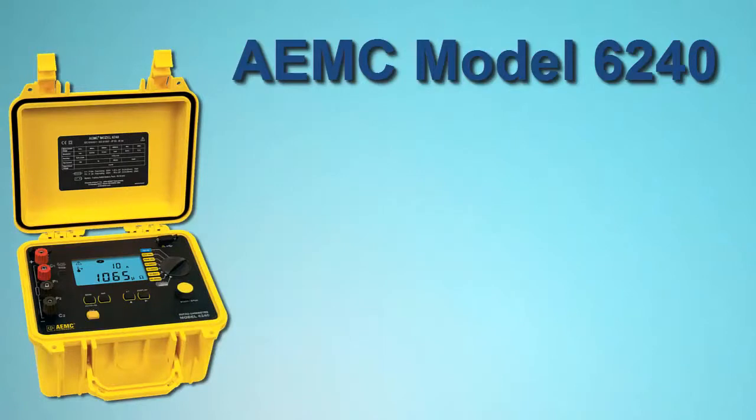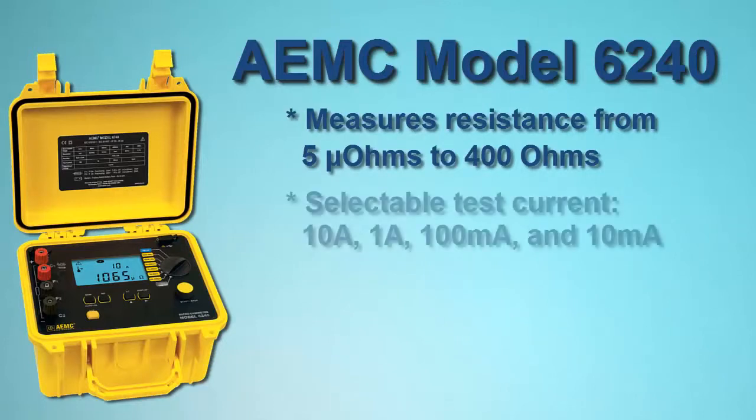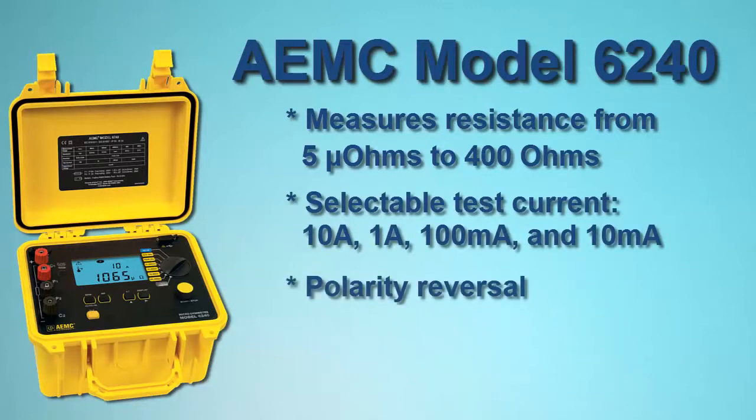The Model 6240 measures resistance from 5 micro-ohms to 400 ohms. The instrument provides selectable test currents of 10 amps, 1 amp, 100 milliamps and 10 milliamps, and includes a polarity reversal function. Up to 99 measurements can be stored in memory.